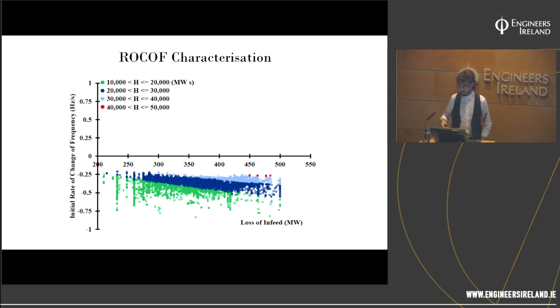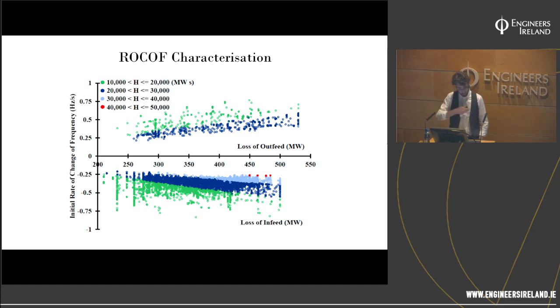But of course, you can also lose an interconnector on export, or you could lose a large load. What I'm showing here are instances where we actually lose an interconnector. These actually occur during low inertia times, because generally we import from Britain, and that's totally defined by the change in the relative price between the two systems. When we have high wind at night, we can start becoming competitive with the Great Britain price. It's a bigger system, so it generally has a lower marginal price of electricity, but when our wind penetrations get up, we can start exporting. Although there are fewer of these events, you could argue that the risk is higher.